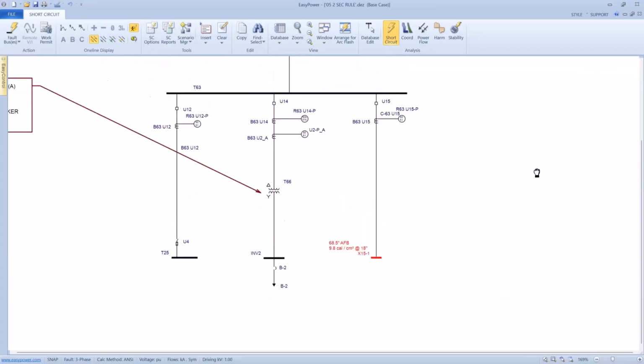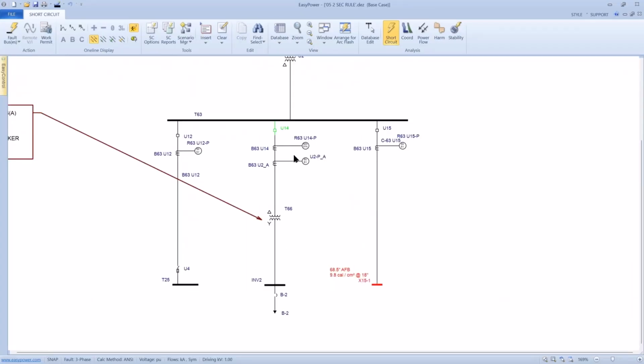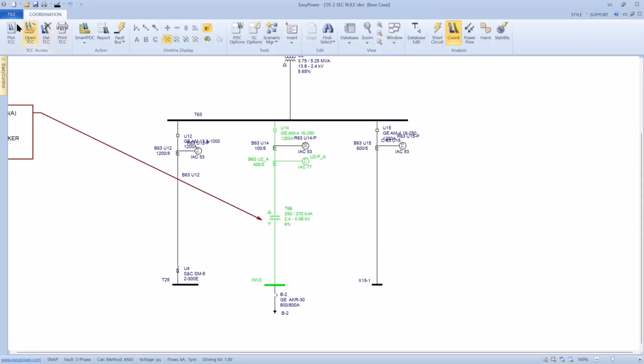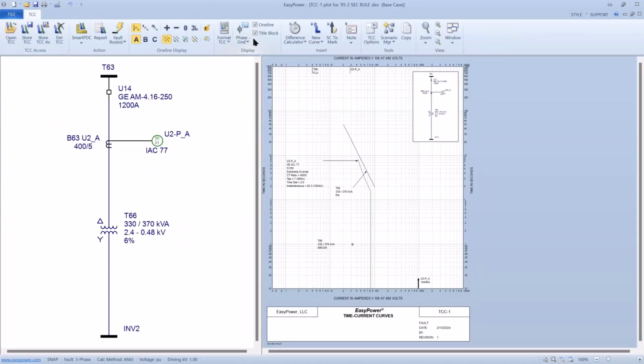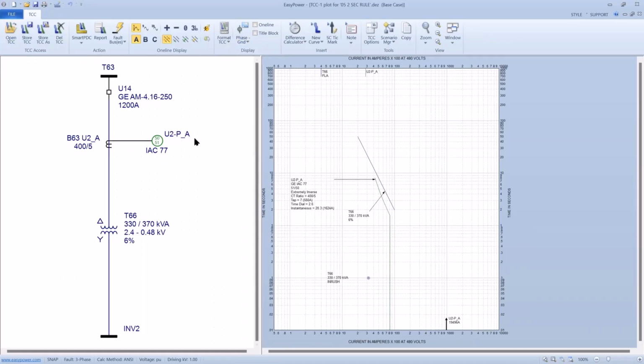So the next thing I'm going to do is look at the coordination. So we're going to skip over ground coordination for right now. Look at this transformer. Now, in this one line, this load was the only thing showing up for this transformer. So let's go into coordination and look at the plot. And what I see is, now this is a 330 kVA transformer rated at 6%. And so I have 6 times the full load current possibility for my protection scheme. And if I look at this line, this is my transformer damage curve, and this is the relay that's protecting downstream.